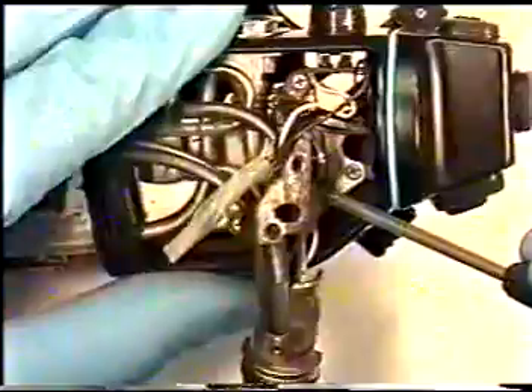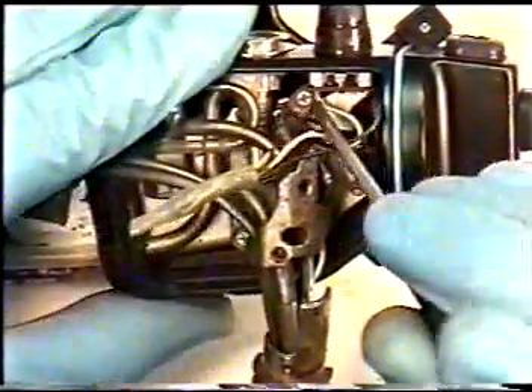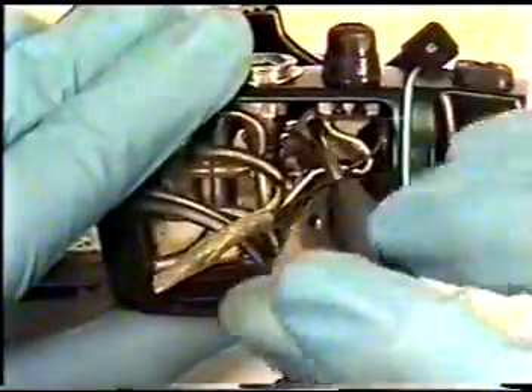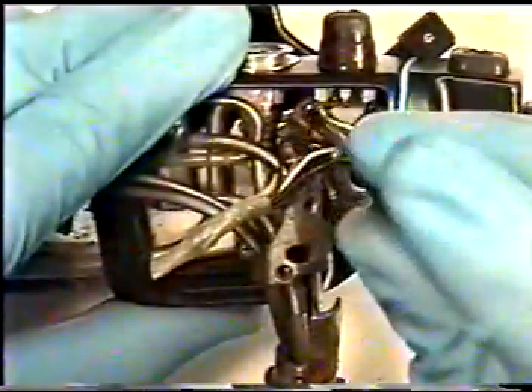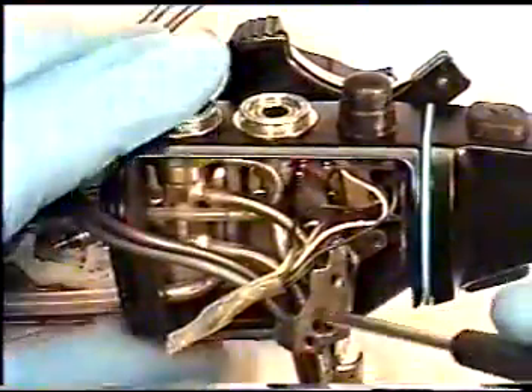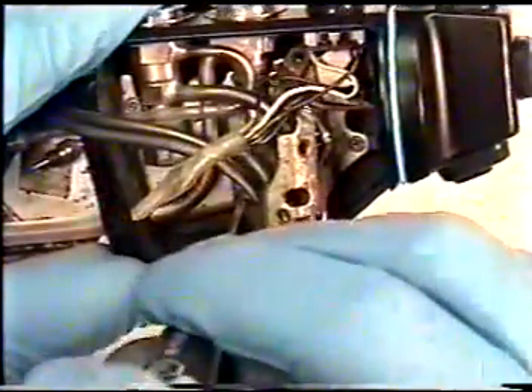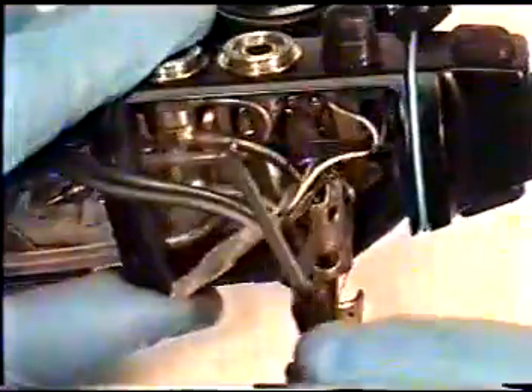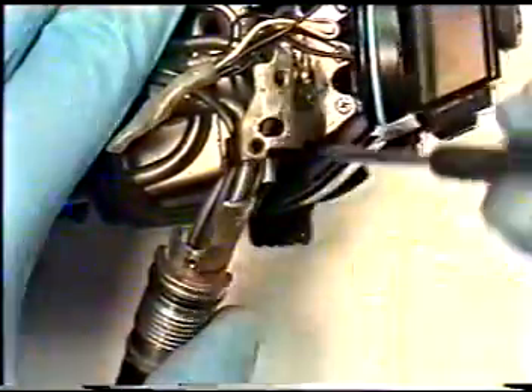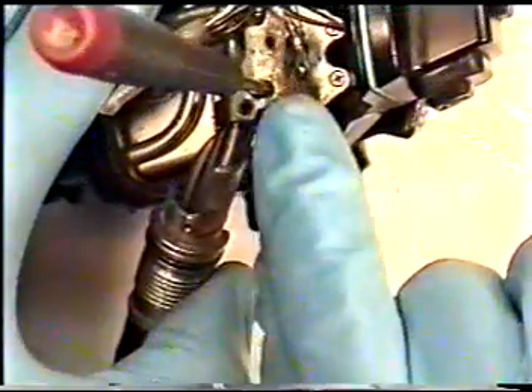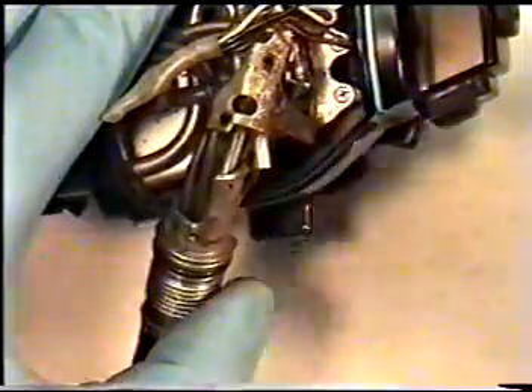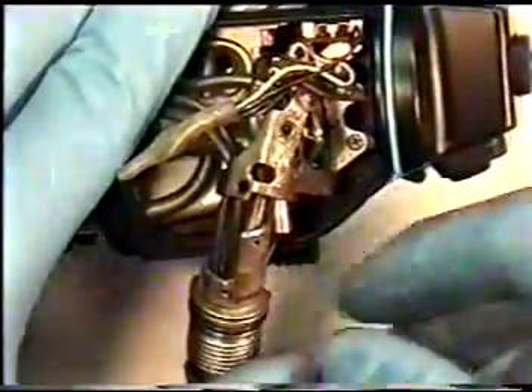There are 3 screws which hold in this control body section plate. First one is at the top. Be careful not to pinch any wires or image bundle if it is a fiber scope. Carefully retain each screw for reassembly. Second screw is along the side, lower left side. Remove the Phillips screw and retain. The last screw, you'll need to insert your Phillips screwdriver through the slot straight down in order to gain access to the Phillips screw, which is located directly below the slot which is cut into your control plate. Carefully unscrew and retain screw. If they fall into body, you will need to turn scope upside down carefully in order to retain screw.